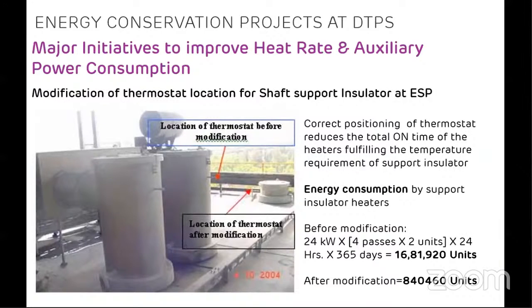Sorry. Basically, mathematical models are used in control systems, but here we are using a very complex system. So for energy conservation purposes, we have benchmarks for individual equipments. For a certain auxiliary, we have a benchmark consumption, and if the consumption deviates above it, the energy management system will trigger a report or alarm, and from that we will get to know. So we will find out the cause and the energy consumption will be reduced. But for this, there is no auto control system. For this, we have to carry out some maintenance or some kind of modification in the system to reduce the consumption.